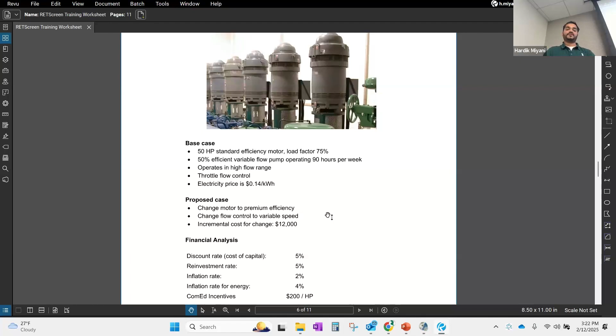In that case, the client says I want to change my pump to premium efficiency as well. So I'm upgrading my pumps to a premium efficiency motor. You see that the efficiency changed from 91.1 to 94. Again, this is from the database that RETScreen has. If you have the actual efficiency for the pumps, or rather the motor, you should enter that to get the actual savings associated with it.